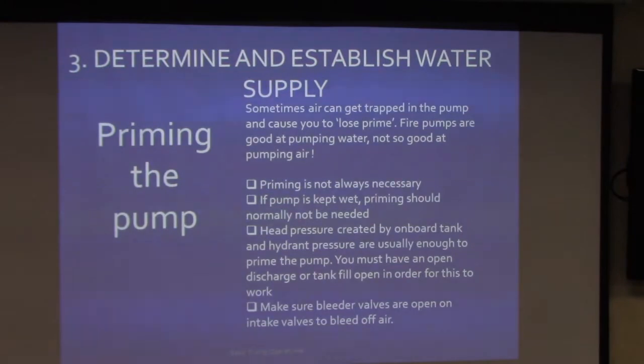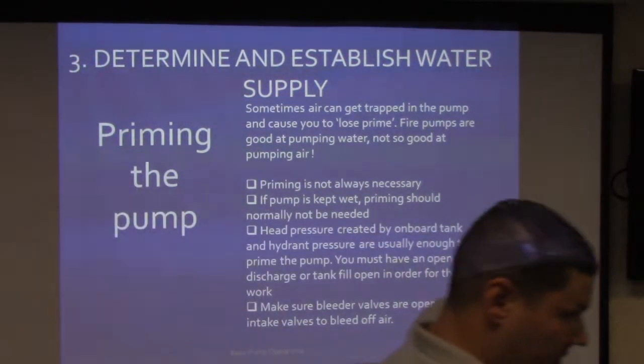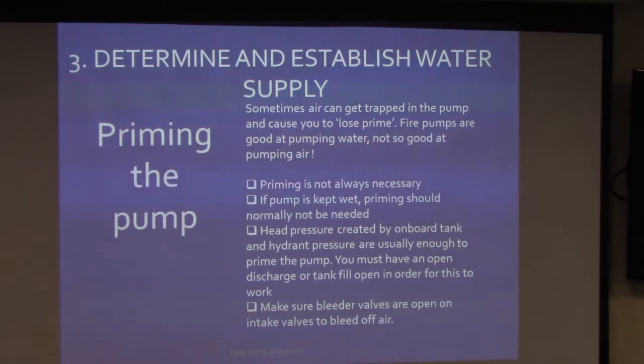Priming the pump—is priming the pump always necessary? We should have a constant prime on the pump since there's water in the pump. Some departments, during the winter, will drain the pump, but we've never done that here. In that case, you'd really have to be concerned about air getting into the system when priming.